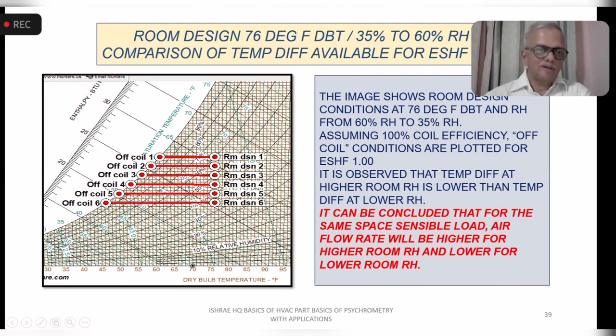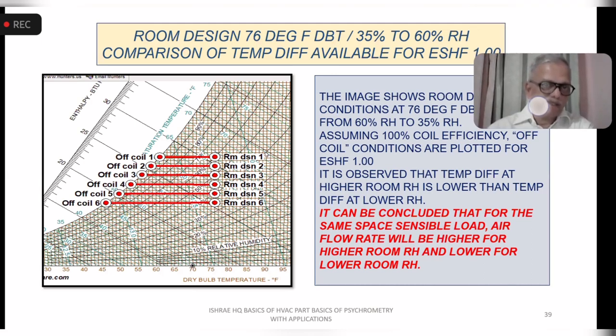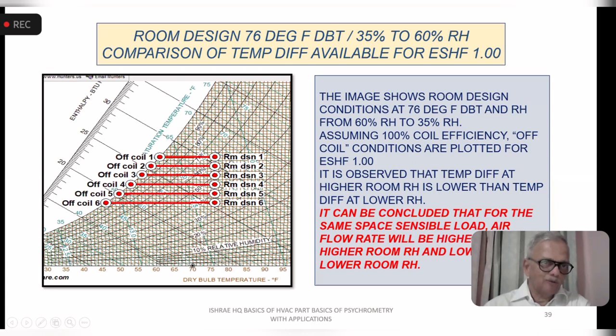The image is showing the room design again, 1 to 6, with the off coil condition, assuming 100% coil efficiency. So it is showing the room design conditions from 76, 60 to 35% RH, and all plotted for an effective sensible heat factor of 1. So you will see the temperature difference, delta T for the heat pickup, is lower here compared to this.